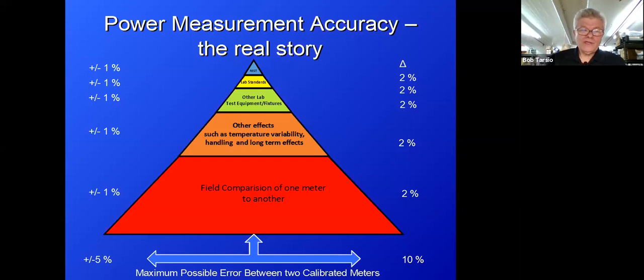But, let's think about what we're doing here, and let's look at some of the sources of error to that. What's the purity of the water? What is the flow rate through the channel? What is the accuracy of the thermometers that are being used for the inlet and outlet temperature? So all of these things stack up to add errors. And if you'll notice, there's another set of errors on the left-hand side there, another plus or minus 1%. Now, that's calorimetry. We don't use calorimetry.